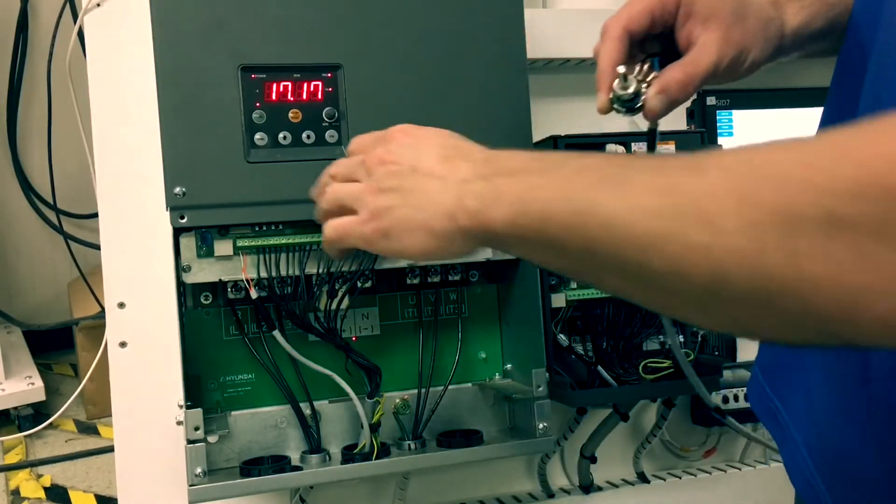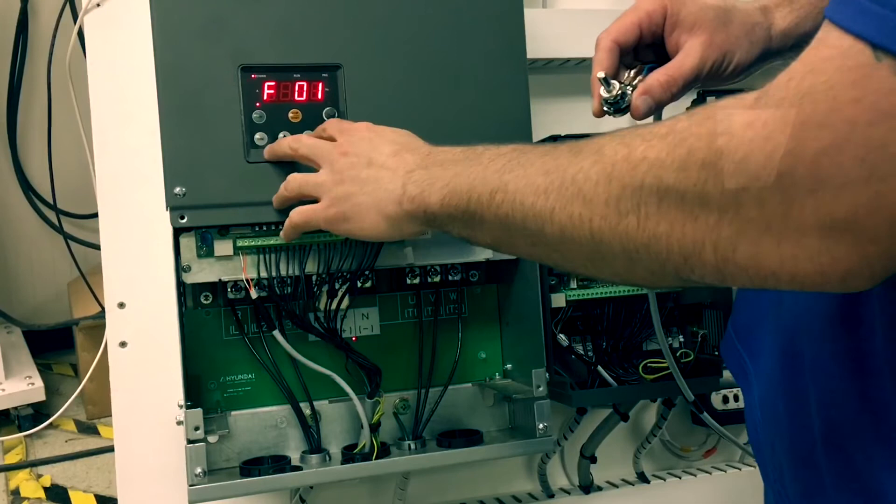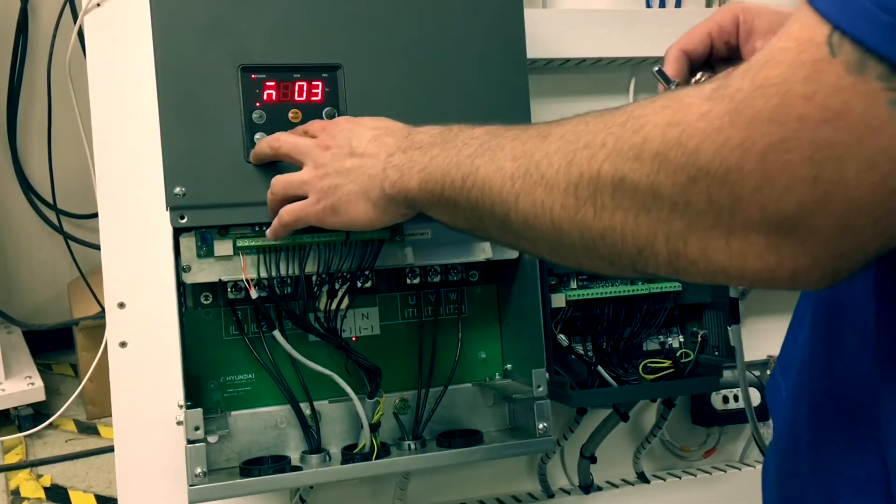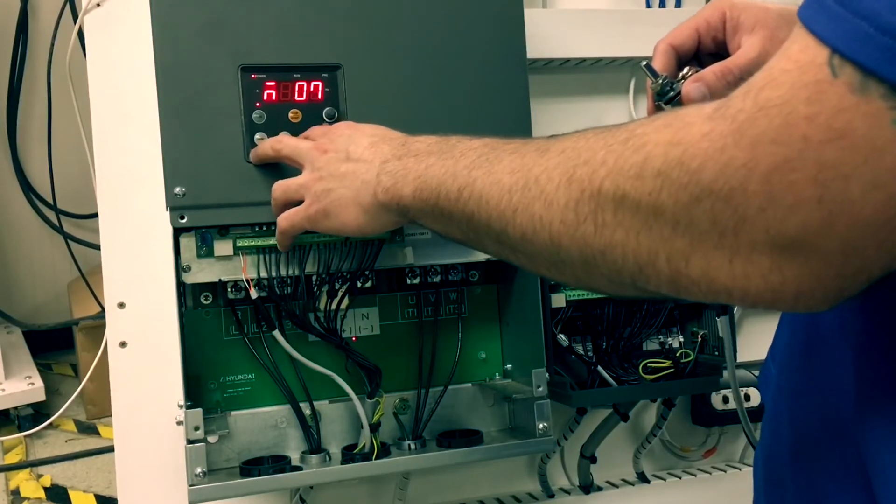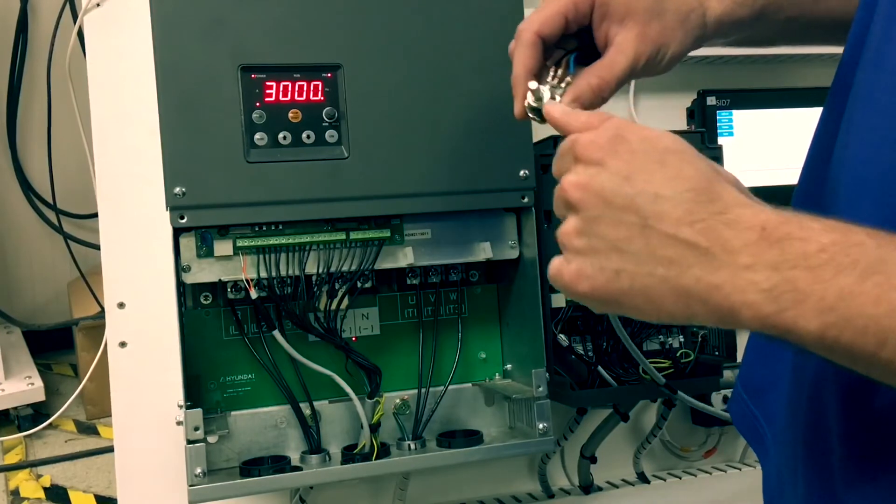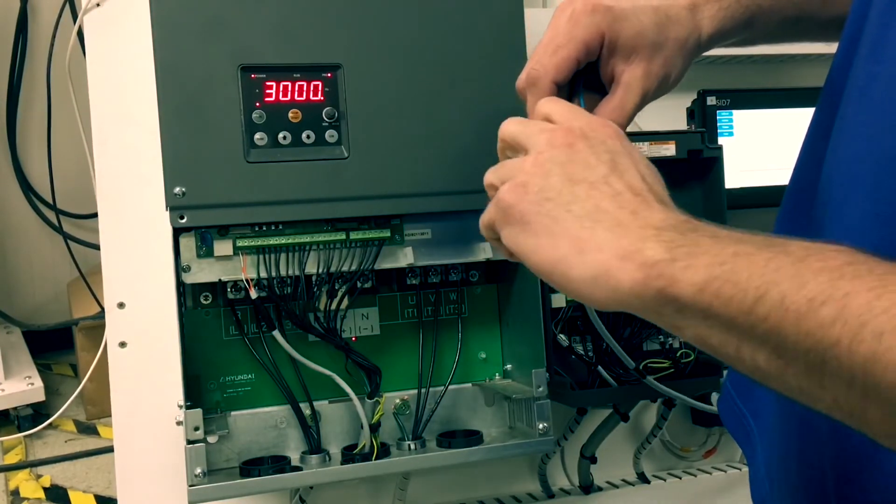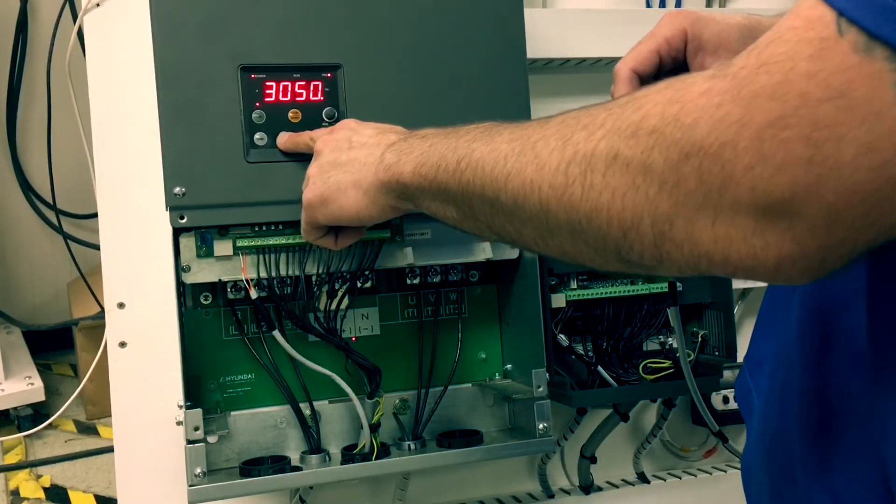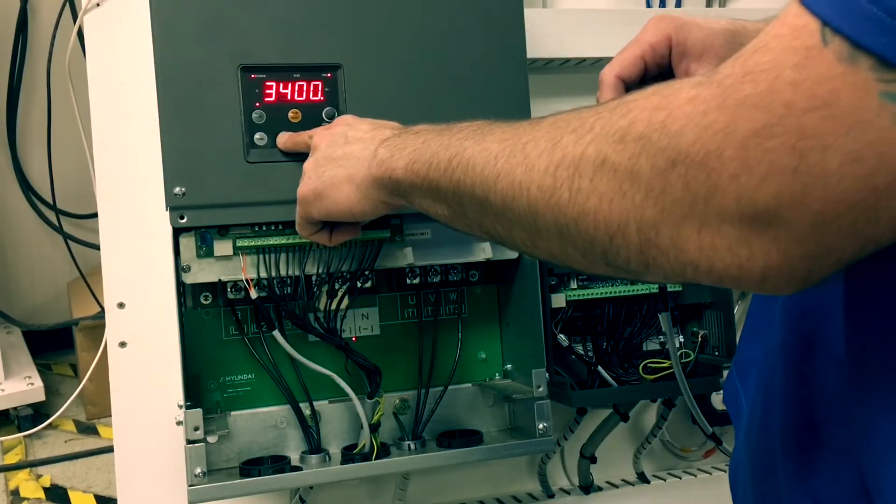First thing we will need to do is go into our M parameters and begin our process of calibration by accessing M07, making sure our speed potentiometer is turned all the way down at 0 volts. Then raise the M07 value to the highest value to 3000 without a dot, then store.